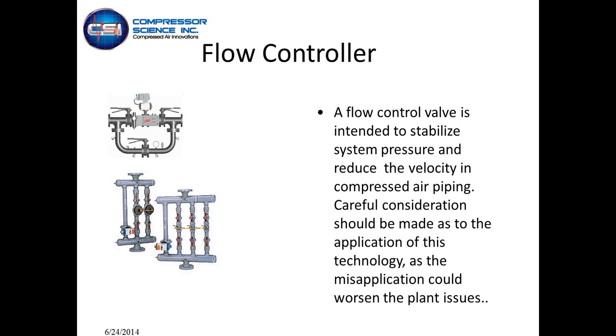That transducer is back at the compressor, so it doesn't necessarily know what's happening at the far end of the plant. It doesn't know that your shot peen's gone off. It doesn't know that your blow-offs are working out in the plant. All it knows is it needs to maintain a certain pressure back in the compressor room based on its set pressure. One advantage of the flow control valve, and again, without storage, a flow control valve doesn't work. You need to have the storage behind it. The principle there is that you should have enough storage behind the flow control valve that you're able to take things like those events that I talked about in the last slide out of the distribution circuit by applying storage to it.